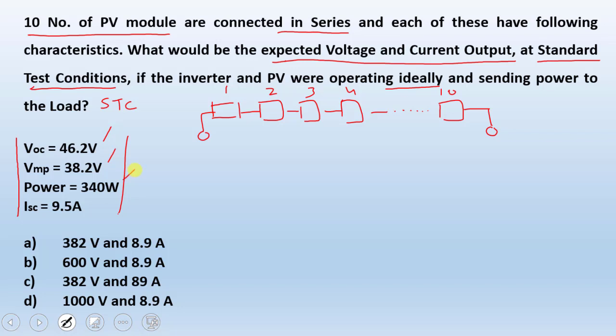And this info is a little tricky. Power 340 watts. Remember one thing is that when a specification is given about a PV module under Standard Test Conditions, then the power is always the maximum power of that module under Standard Test Conditions.